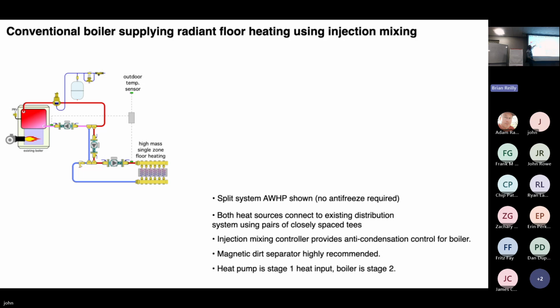But as we start to increase the speed of the circulator, we start injecting hot water, and that mixes with some of the cool water coming back around through here. So we've got these 2 streams coming together in this T. Depending on how fast the hot water is being injected relative to this flow rate, we can control the water temperature going to the load, to the heat emitters. There's thousands of systems in North America that are using this kind of setup.